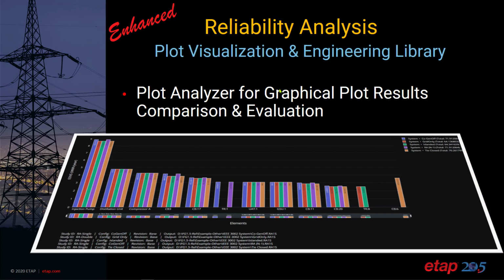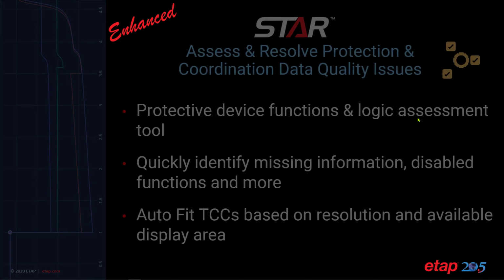Reliability analysis has also been enhanced to include the plot analyzer for graphical plot comparison. And one of the typical applications for this would be to perform sensitivity analysis across different conditions, across different single or double contingencies, and looking at the most sensitive components and the impact of the reliability of having an outage on these components. And based on different conditions, you can then quickly isolate which are your most critical components that require higher redundancy or reliability across many different what-if cases.